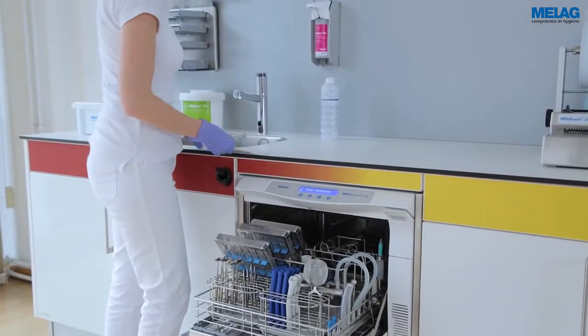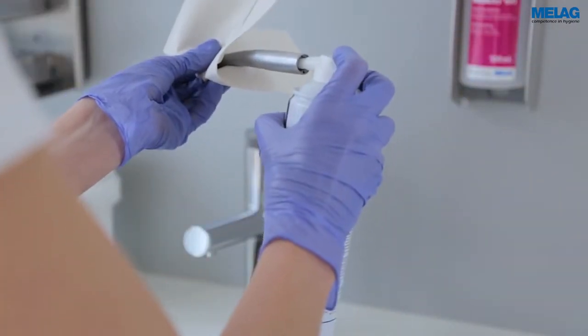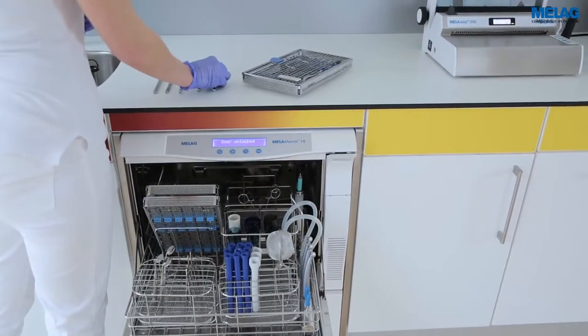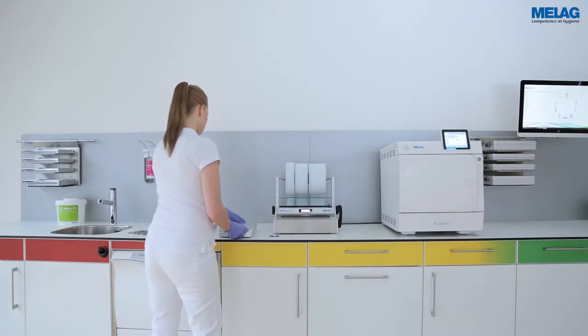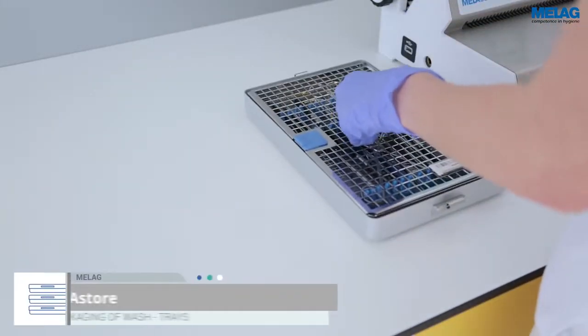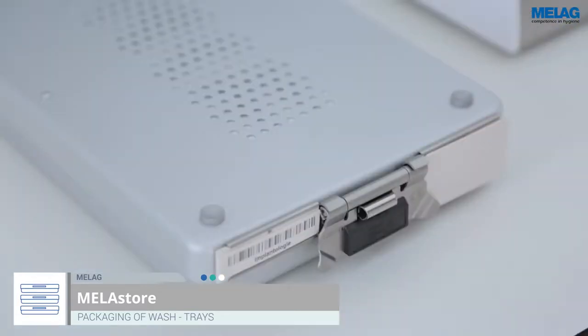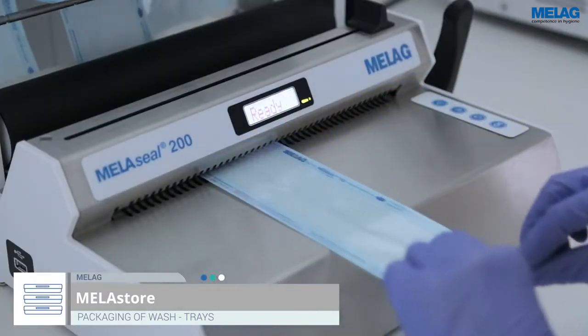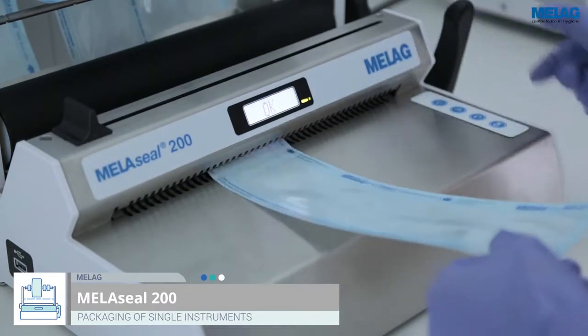Handpieces and turbines in particular require specialist care in lubrication in compliance with the manufacturer's specifications. Surgical instruments have to be wrapped for the sterilisation. The use of MELAstore trays and MELAstore boxes optimises workflows, leading to considerable improvements in working safety, reproducibility and efficiency. Individual instruments are wrapped in MeLafol.